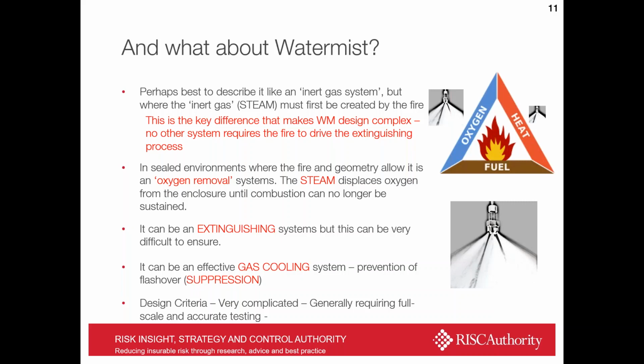Now, in sealed environments where the fire and geometry allow it, it is most certainly an oxygen removal system, and you can achieve great things where the steam displaces oxygen from the enclosure until combustion can no longer be sustained. It can be an extinguishing system, but this can be very difficult to ensure due to the level of control that you need over the environment and how everything goes. But I'll demonstrate that very clearly to you shortly with some results from some experiments that we conducted to demonstrate these points. It's obviously a very effective gas cooling system.